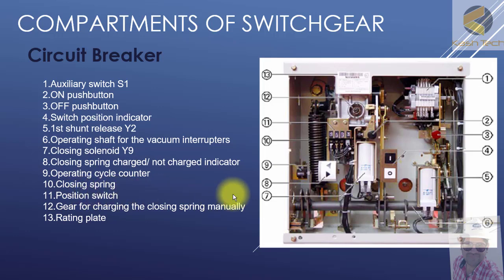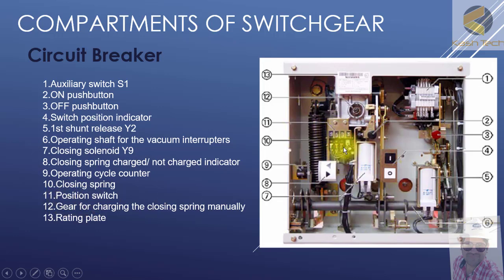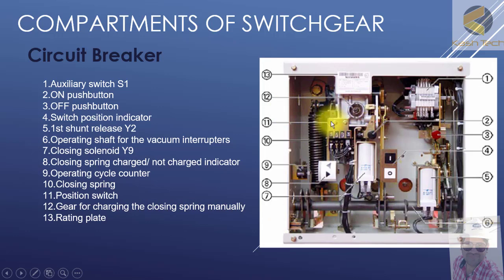Number ten is the closing spring — this is an example of a closing spring of the circuit breaker. Number eleven is the position switch. Number twelve is a gear for charging the closing spring manually. For example, if the motor has failed or there is no supply and you want to close the breaker, you can charge the spring through this gear by putting a lever here and then operating the breaker.